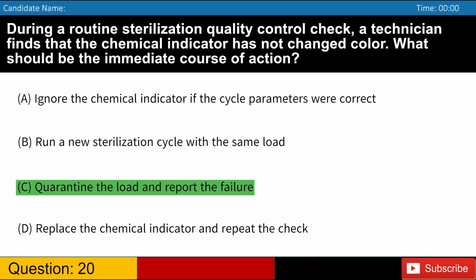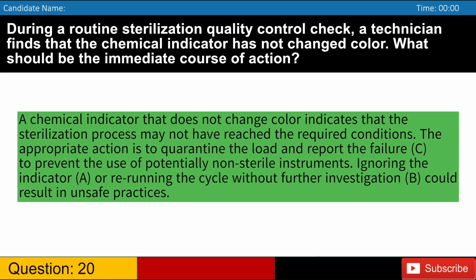Answer, C. A chemical indicator that does not change color indicates that the sterilization process may not have reached the required conditions. The appropriate action is to quarantine the load and report the failure, C, to prevent the use of potentially non-sterile instruments. Ignoring the indicator, A, or rerunning the cycle without further investigation, B, could result in unsafe practices.